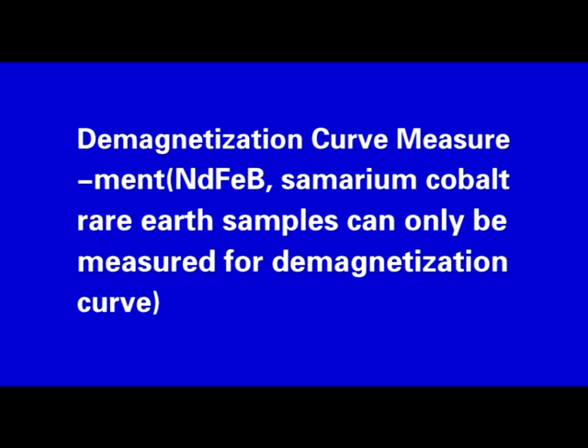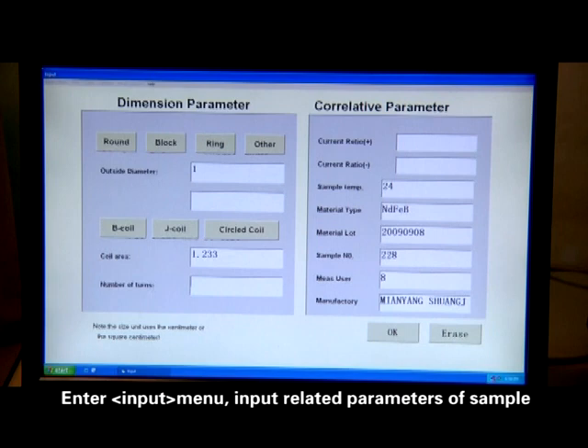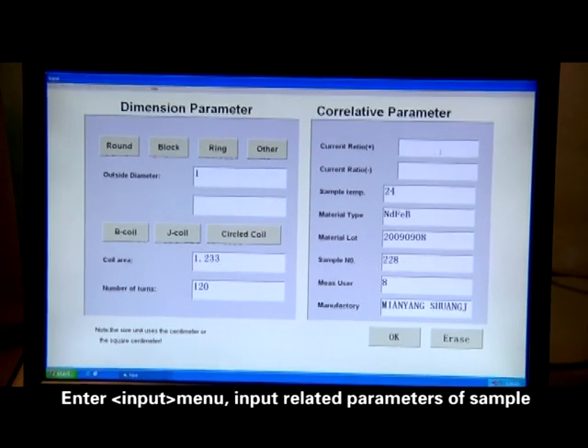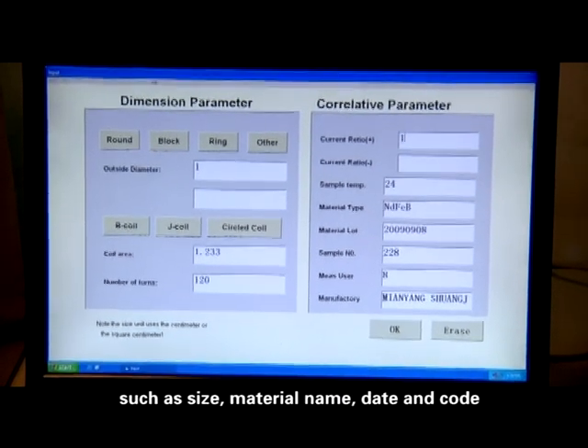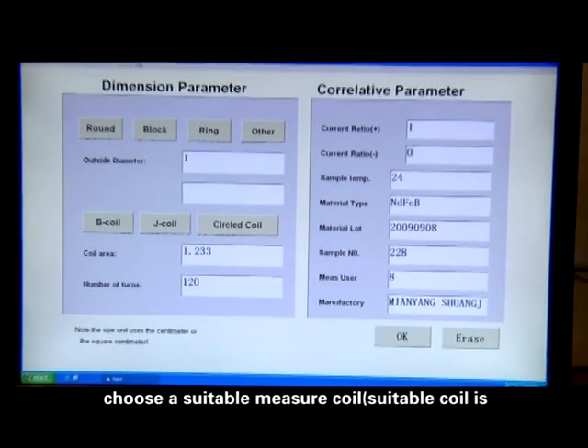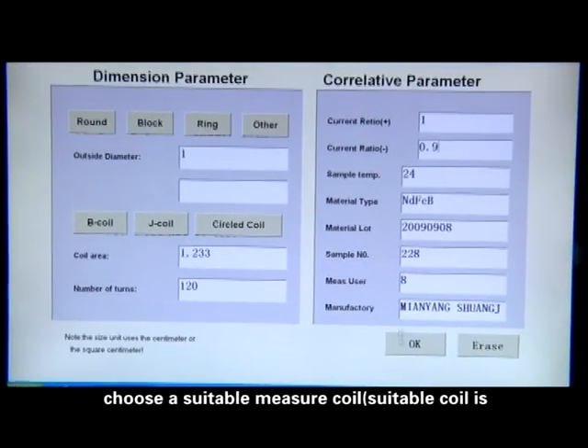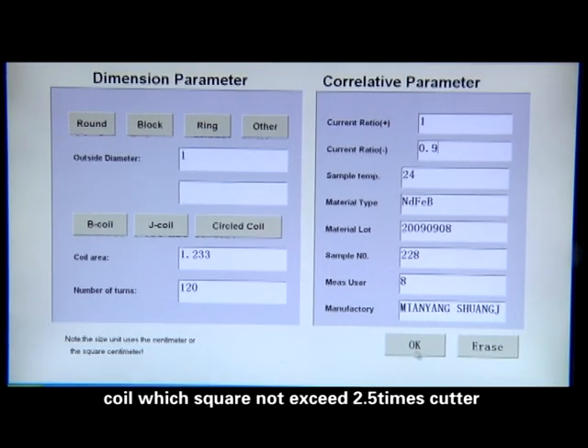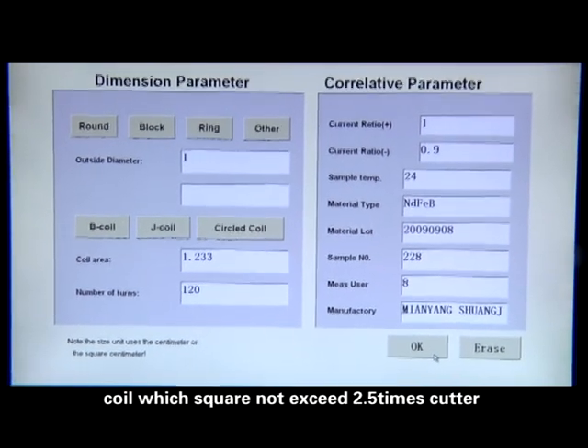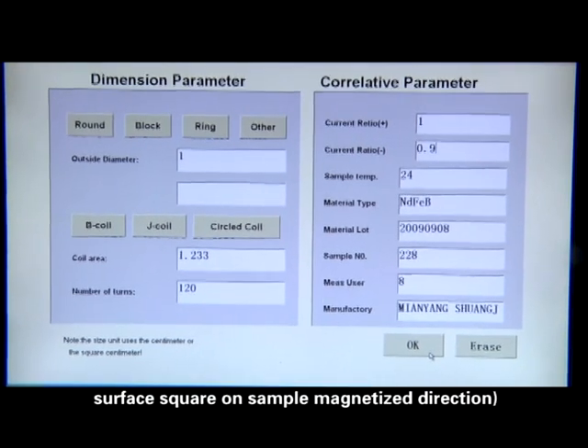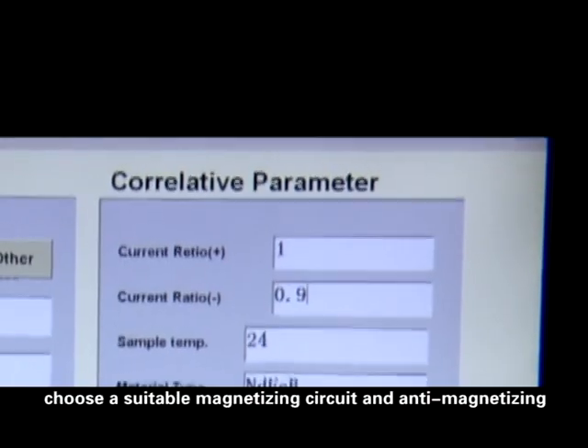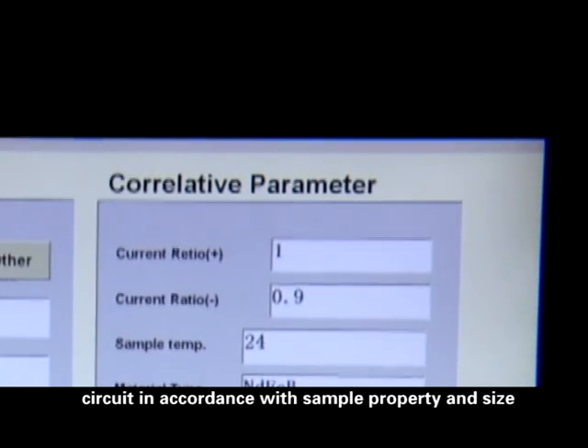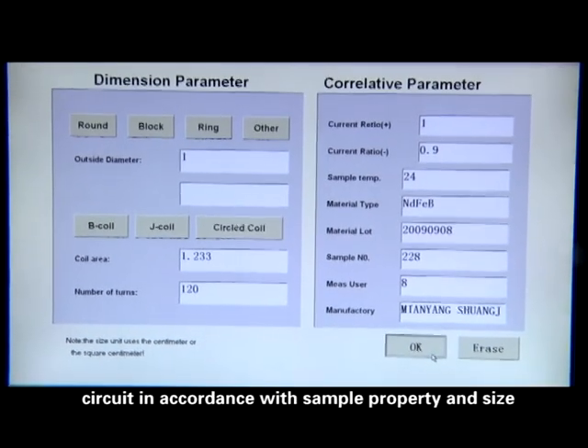Demagnetization curve measurement. NdFeB and samarium cobalt rare earth samples can only be measured for demagnetization curve. Enter input menu. Input related parameters of sample, such as size, material name, data, and code. Choose the suitable measure coil. Suitable coil is coil whose square does not exceed 2.5 times cutter surface square on sample magnetized direction. Choose a suitable magnetizing circuit and anti-magnetizing circuit in accordance with the sample property and size.